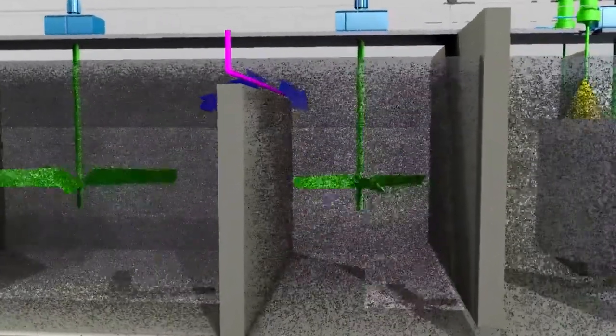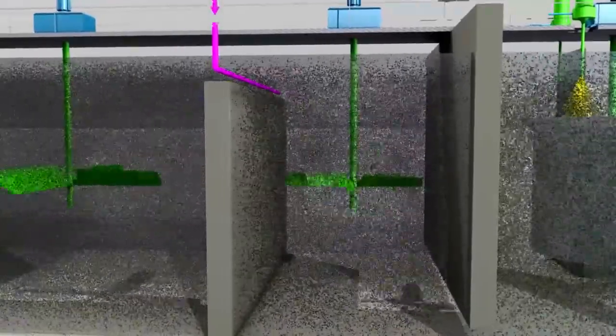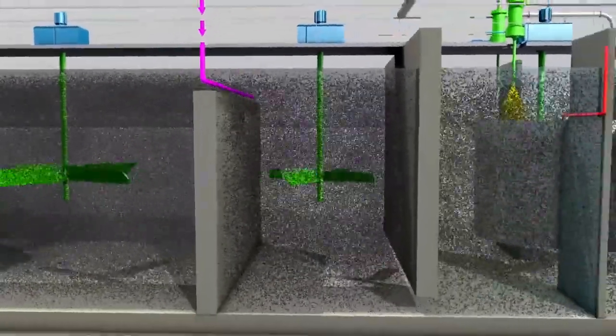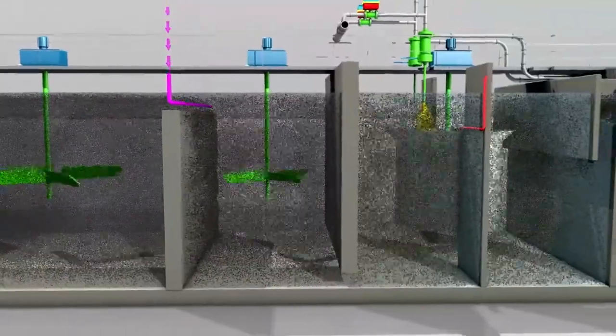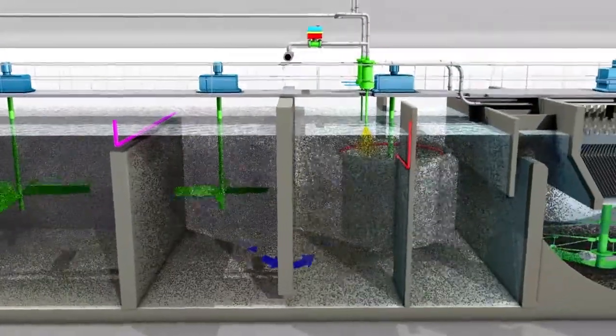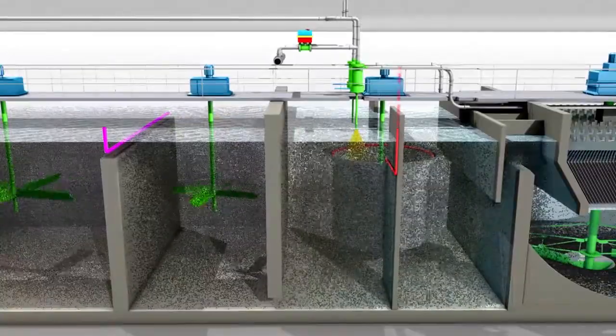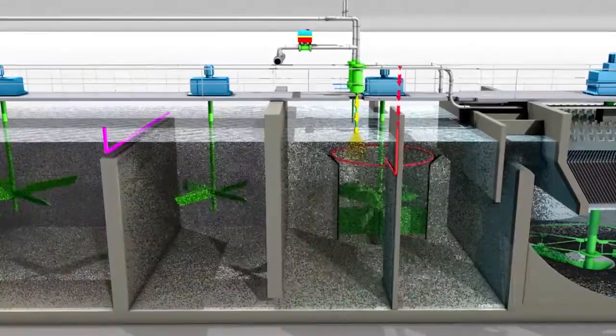Upon the transfer of water to the subsequent rapid mix tank, a coagulant is added to initiate the coagulation reaction. The water then enters the flocculation tank, in which polymer and micro sand are added under intimate mixing conditions.